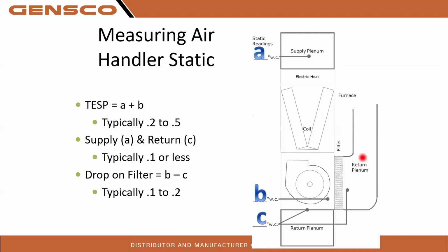Keep in mind, I have seen where these returns, and maybe on the inside of these units, the sound liner has actually come unglued and they didn't have any pins. Watch for that. A good way to detect that without tearing apart your ductwork is take your return air plenum static pressure, because it'll flop in place at idle. So if you were to take this filter out and you're looking in, you don't see anything wrong. But as soon as you start that blower motor, it'll suck into the filter. It could appear further upstream in the return. Yeah, those are hard ones to find sometimes.